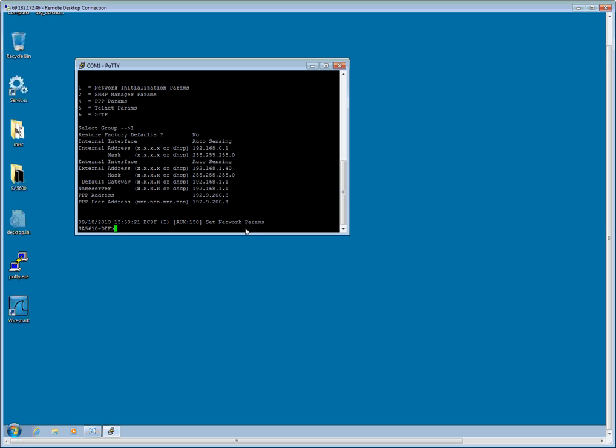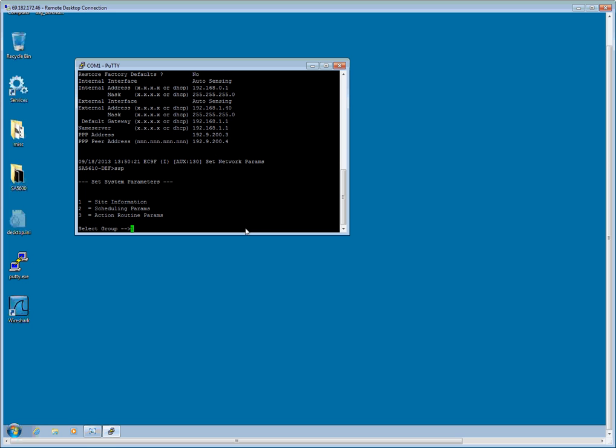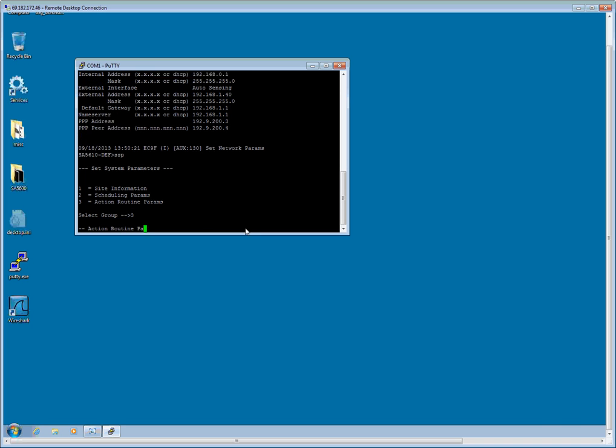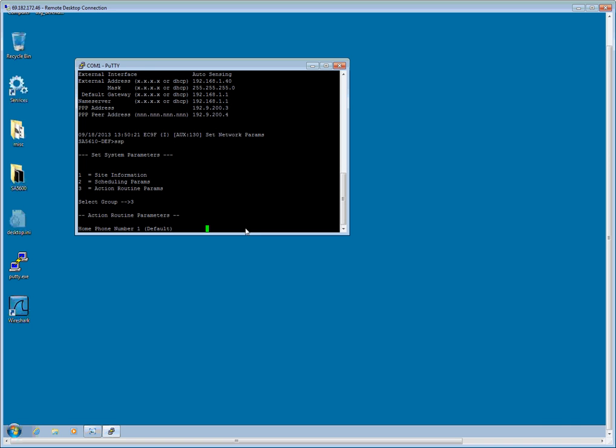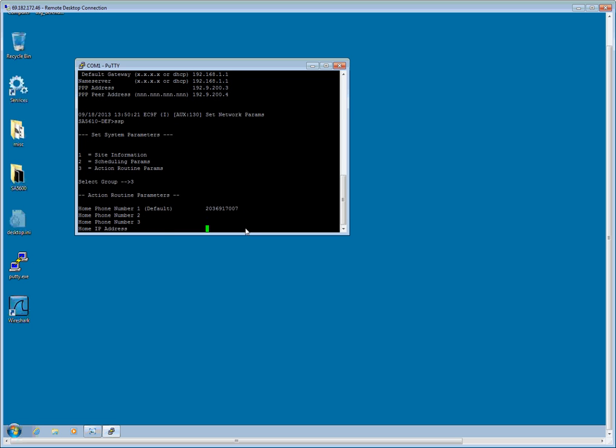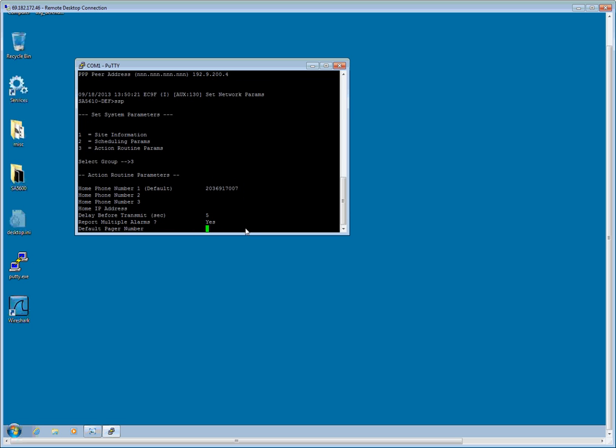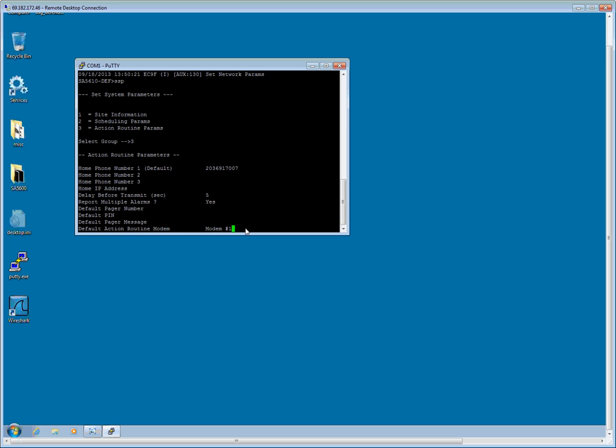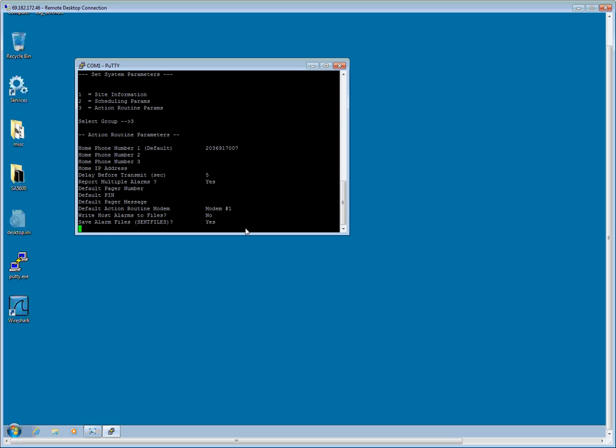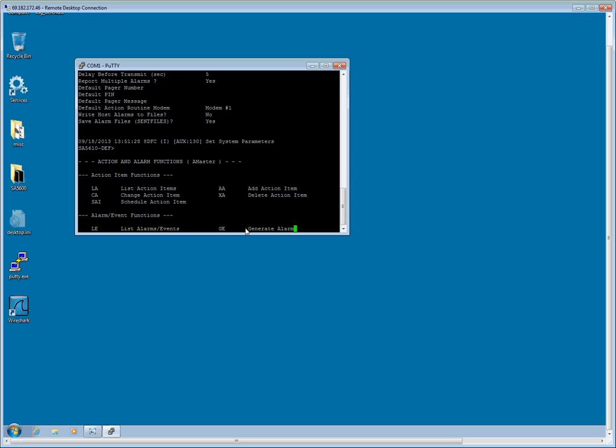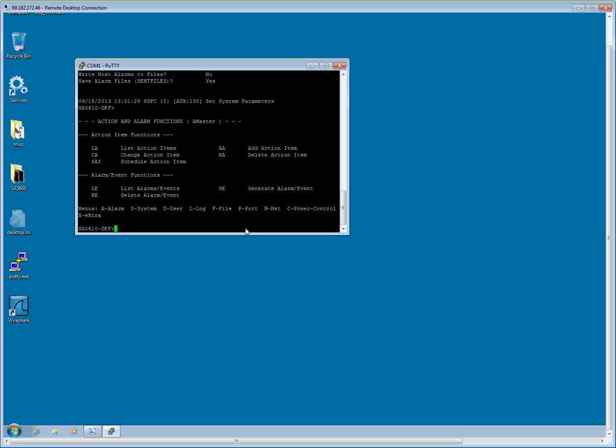The second command is SSP for set system parameters. And the only option we are concerned with here is the action routine parameters. So I am going to press 3. And I am going to enter the telephone number of the alarm track server located back at my NOC. I am going to enter it exactly the way the line needs to be dialed from the modem. So if I need to insert a 9 ahead of the phone number, this is where I do it. In my case, I am just going to enter 203-691-7007. I can leave everything else as default. All right, great. That took.